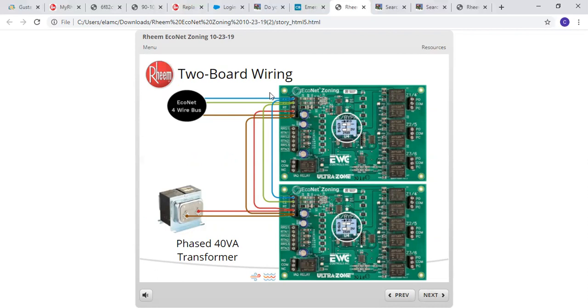Now, if you're going to do a 2-board wiring with an additional transformer here, you'll see we'll come off our Econet bus, E1, E2, and we're going to jump down from here, E1, E2. We will bring our equipment common in, the brown here, into our common. Now we're going to bring our secondary transformer into the second board. So we're going to go common, and we're going to jump that up to our main board common, and we're going to bring our R to the secondary board. We're going to jump that up to our primary board. That simple. Just remember, if you're going to add a secondary transformer, do not bring the equipment R in to the zone board.